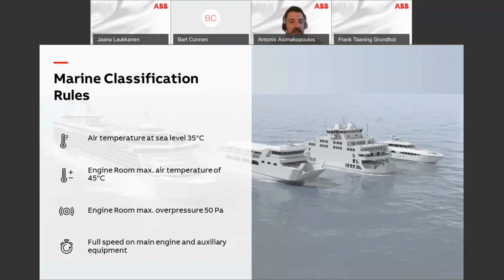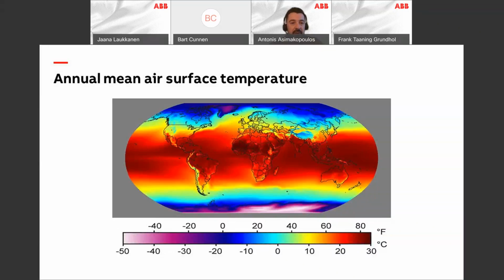A few things about marine classification rules. In general, in the design phase of a vessel, we consider the air temperature around 35 degrees, the engine room maximum air temperature at 45 degrees, and the engine room overpressure at 50 Pascal. Also, we consider full speed on main engine and auxiliary equipment. Let's see a little bit the mean air temperature around the world. As you will see, we don't have a constant temperature. It can vary from 0 degrees to 30 plus degrees around the world. So it depends on where the vessel is operating.